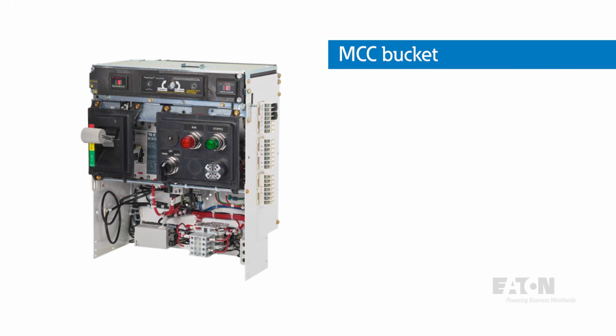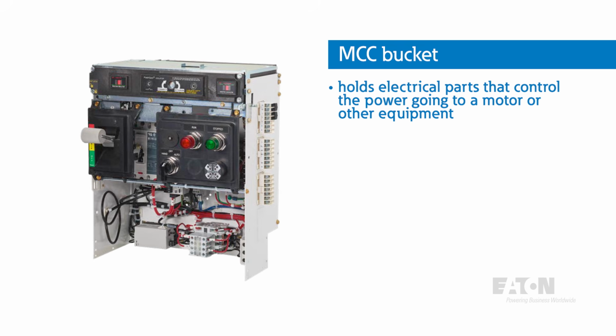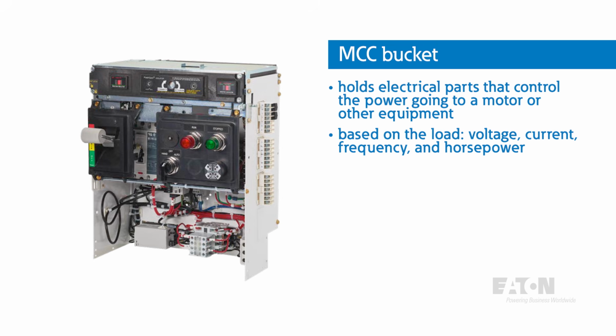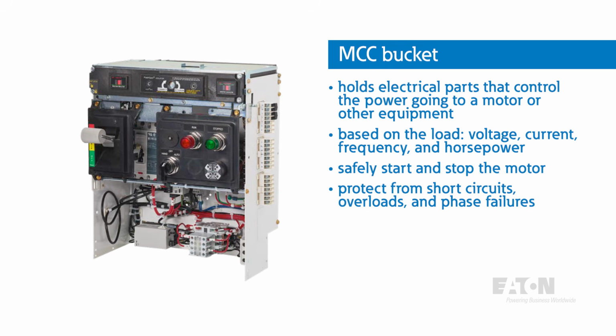Each bucket in an MCC holds electrical parts that control the power going to a motor or other equipment. These parts are chosen based on the load, like voltage, current, frequency, and horsepower. The main job of these components is to safely start and stop the motor and protect it from problems like short circuits, overloads, and phase failures, which can cause serious damage.